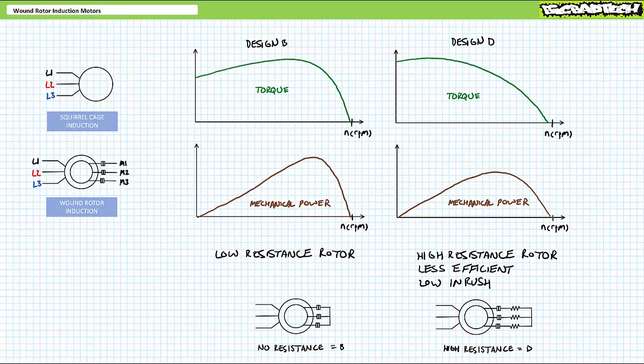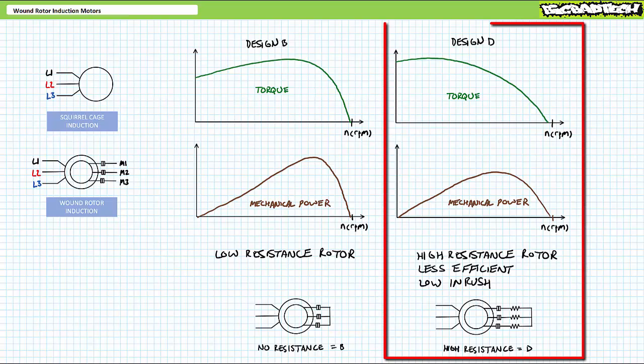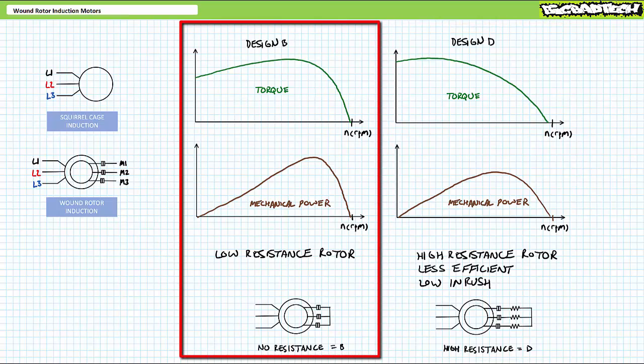Allow me to demonstrate. Let's first examine the two different extremes of operation. Consider three fixed resistors in Y configuration connected to the rotor slip rings. It's important to realize this bank of resistors is stationary and external to the rotor. However, because the slip rings are continuously included in the rotor circuit in series with the rotor windings regardless of the physical orientation of the rotor, with the resistors in the rotor circuit, the motor behaves just like a design D squirrel cage induction motor exhibiting high torque at low speeds and lower inrush current at startup, though it will operate slightly less efficiently. In contrast, when the rotor slip ring connections are tied together as in the central node of a Y configuration, this is a low resistance configuration where only the natural resistance of the rotor windings is considered. With no additional resistance in the rotor circuit, the motor behaves just like a design B squirrel cage induction motor exhibiting more efficient operation at higher speeds.